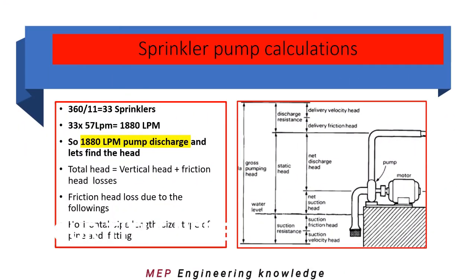Let us have an example: the area of operation is 360 square meters and we are using sprinkler coverage averaging 10 to 12 square meters. So 360 divided by 11 gives 33 sprinklers. We know each sprinkler will have 57 LPM discharge, so when we multiply we get 1880 LPM — that is the pump discharge we need to select.